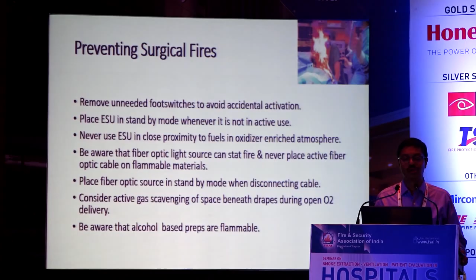How to respond? Maybe it has been touched upon in the morning session, but if it has, I can skip. Please let me know, or should I continue on this slide? Okay. The content has been taken from ECRI. A small fire due to the electrosurgical unit pencil is extinguished by patting the fire with a gloved hand or towel. If it is a large fire, stop the flow of the oxidizer to the patient. Remove the burning material from the patient and extinguish it.